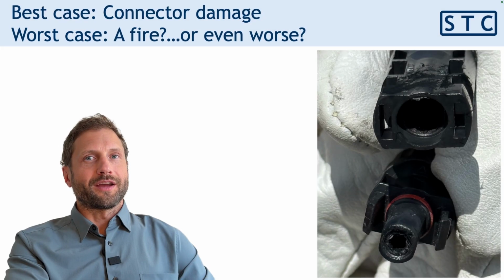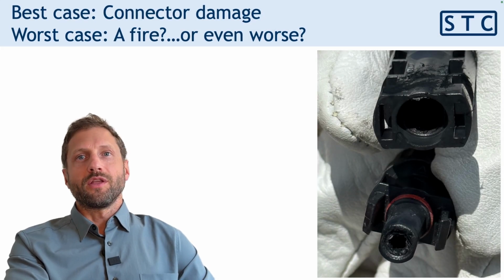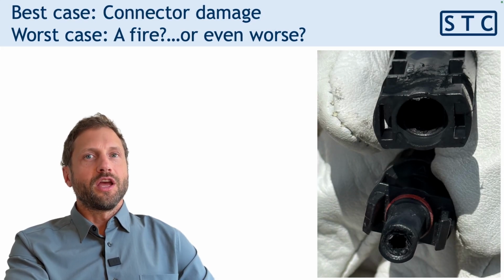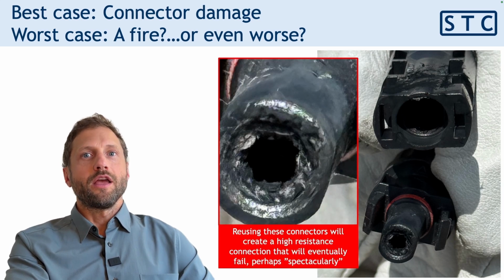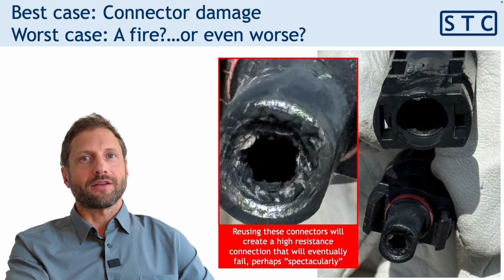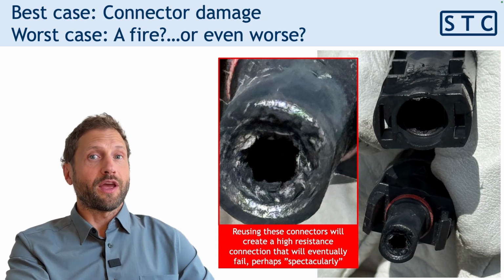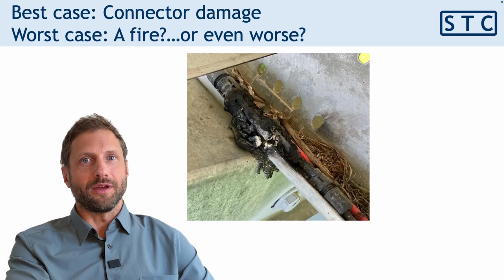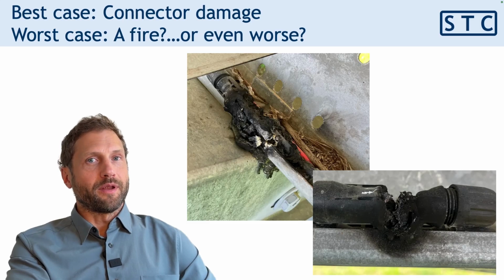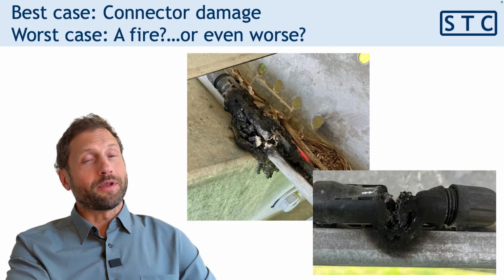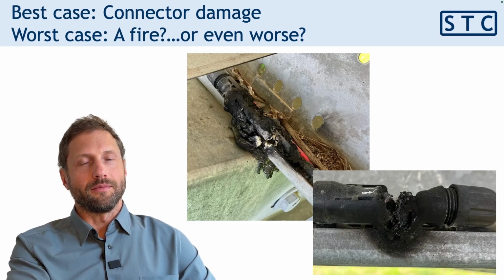This is what those connectors look like afterwards. You can see that there was significant damage, but the worst damage isn't visible because it happened to the current carrying parts inside. If we were to reuse these connectors, they'll have a high resistance connection that'll eventually fail, perhaps spectacularly. But this isn't the worst that could happen. It could lead to a fire or potentially harm someone on site.